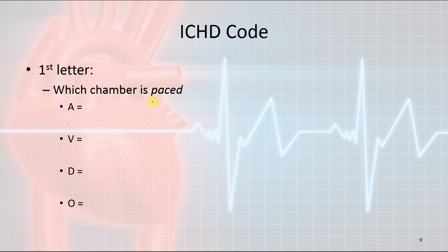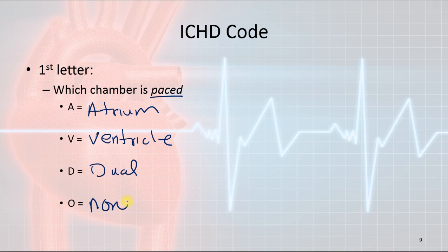The first letter is the chamber that is paced. This is simple. The A stands for atrium. The V stands for ventricle. D is for dual, which means it paces the atrium and the ventricle. O is set to none, which means it would not pace the atrium or the ventricle. Different doctors have different reasons to set it up for it to not pace. Maybe it's not a pacemaker, maybe it is a cardioverter defibrillator. But the first letter stands for which chamber is paced.